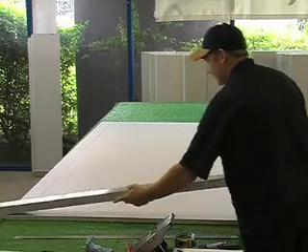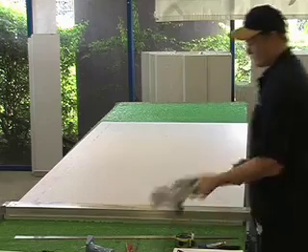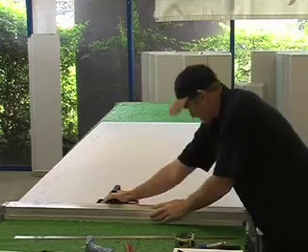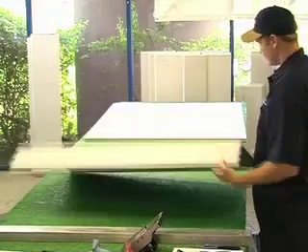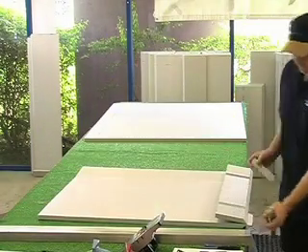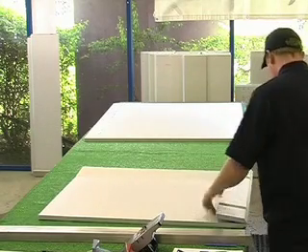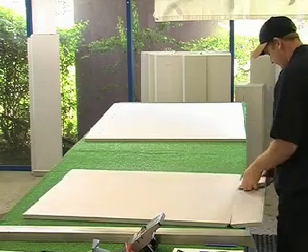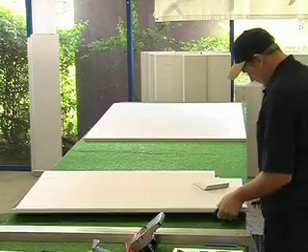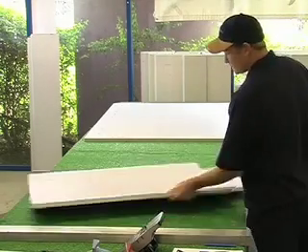Air conditioning ductwork constructed from Polypanel becomes a viable alternative to mild steel duct from the moment of manufacture. Simple tools, some space and the ability to cut straight are really all that is needed to make quite complex shapes. The basic tools are a cutting table, straight edge, 3 special knives, 45 degree, straight cut, and the double 45 degree or mitre for cutting 90-degree folds.